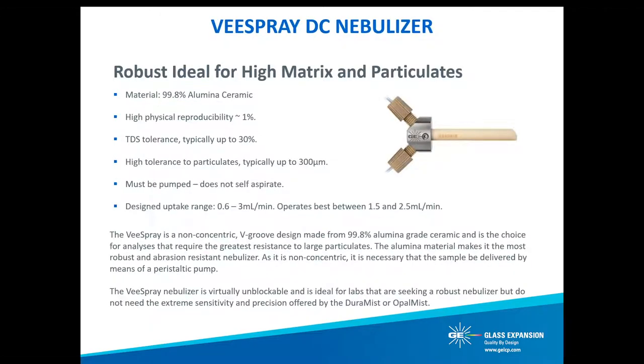The last nebulizer we'll introduce is Glass Expansion's only non-concentric design: the VeeSpray. It's a v-groove design made from high-purity alumina-grade ceramic. It's a good choice for analyses requiring the greatest resistance to large particulates — it can typically pass through up to 300 micron particulates. The alumina material makes it the most robust and abrasion-resistant nebulizer. As it's non-concentric, sample must be delivered by peristaltic pump, and it operates optimally at a higher uptake rate range between 1.5 and 2.5 mils per minute. The VeeSpray is virtually unblockable and ideal for labs seeking robustness without requiring the extreme sensitivity of the DuraMist or OpalMist.